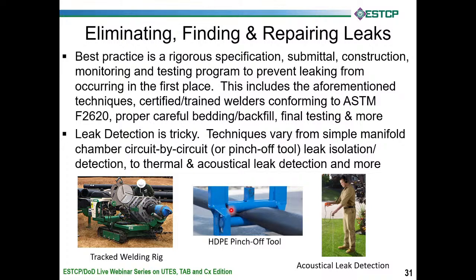On our BTES systems, we typically only have 3 zones, so there's only 3 boreholes per circuit. But on a conventional geothermal system, you might have dozens of boreholes per circuit. But in any event, you want to first isolate it down to the circuit that is leaking. And then what kind of techniques do you use to find it?